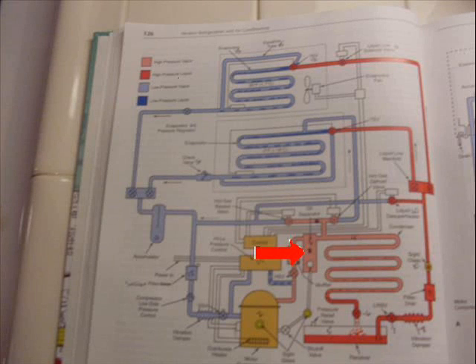We go to the oil separator. There are two types of oil separators. Type number one is a helical style that has an internal vortex that causes the refrigerant to spin inside. The heavier oil molecules are thrown against the outside of the oil separator where they slide down along the walls and accumulate in the bottom.